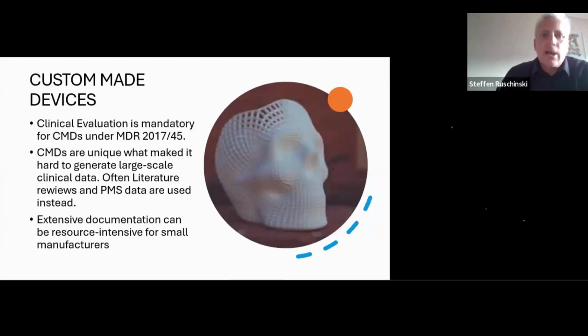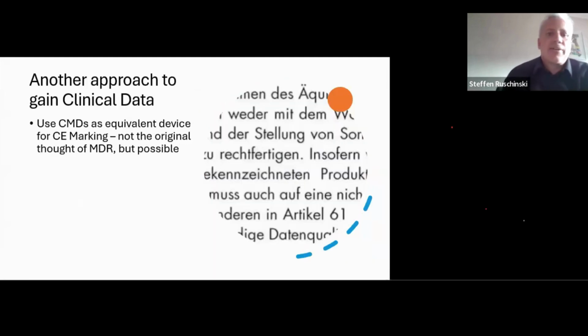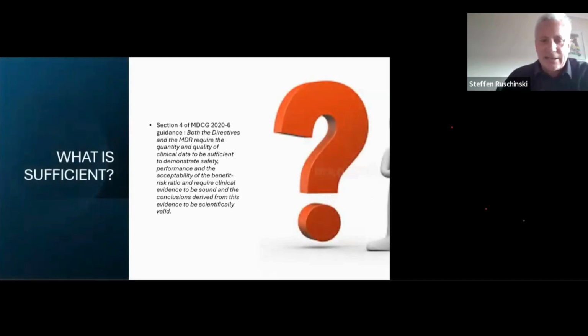Custom-made devices are also subject to clinical evaluation under MDR 2017/745. They're unique, which makes it very hard to generate large-scale clinical data. Often literature reviews and PMS data are used instead, and extensive documentation can be resource-intensive for small manufacturers. Anyway, there's still another approach to gain clinical data via CMDs, as they can be used as an equivalent device for CE marking, which is not the original thought of the MDR, but is legally possible.